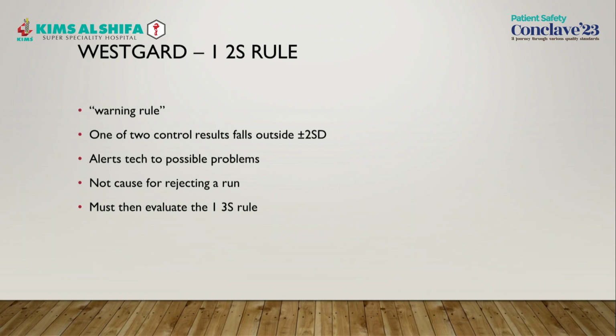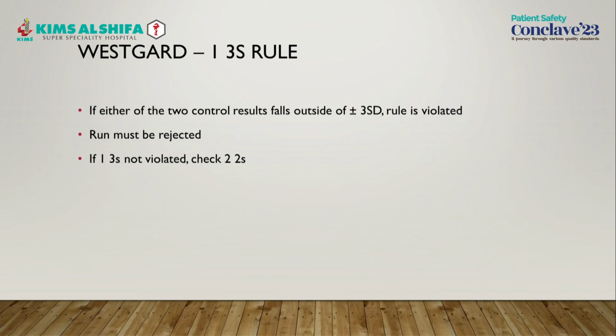When one of your two control results falls outside plus or minus 2 SD, it's a warning rule, so you should be cautious about that parameter. And when 1-3S comes, the run must be rejected. You cannot release results if the IQC of any of your parameters in the lab falls outside plus or minus 3 SD.